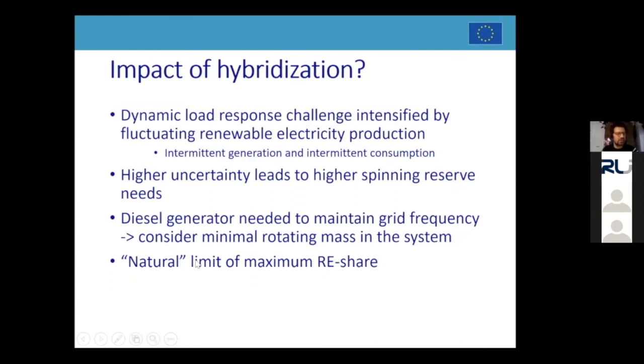So now let's think about the impact of hybridization. So we see that a diesel-only system is already complex. So the diesel generators, as we said, need to not only cover the demand, but you need to fulfill certain stability criteria. You need to have enough spinning reserve and so on. And you always have uncertainty about the demand. You have your demand projections, like your daily projections, and also your annual projections, but always something unexpected can happen, so that too many people together switch on their washing machine, or like there's an unexpected holiday or something like this, and you always need to react with your generation to the changes in demand.